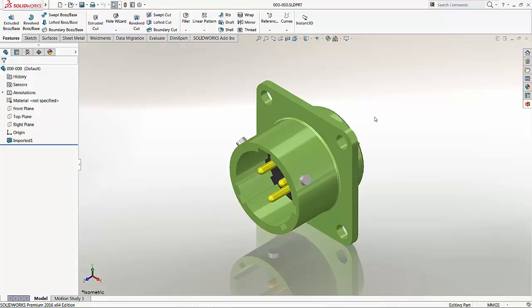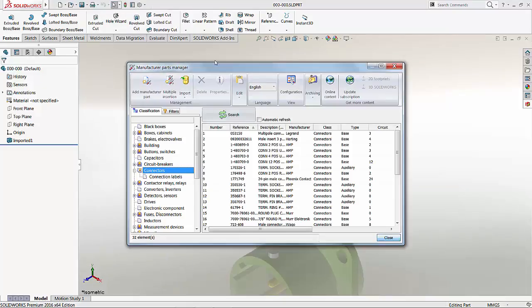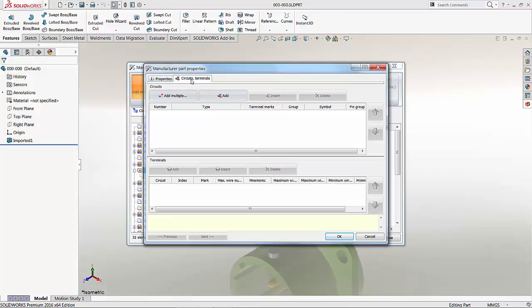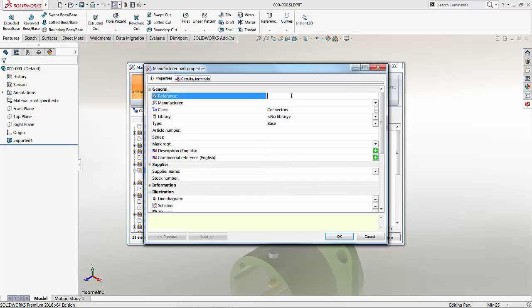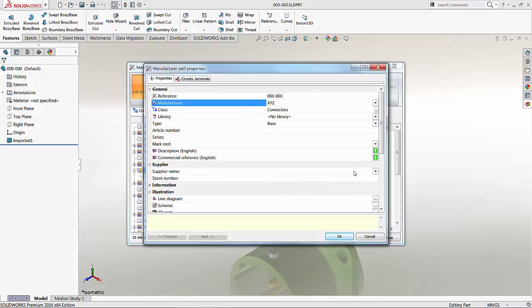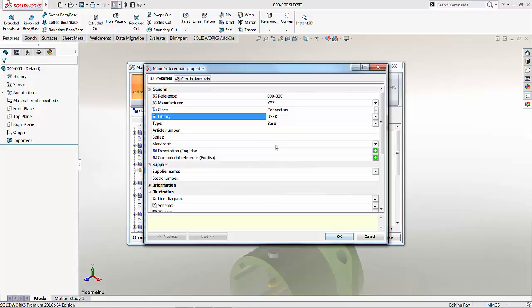Next, I'm going to go to Tools, SOLIDWORKS Electrical, Manufacturer Parts Manager. This process can be carried out either in the schematic or electrical 2D, or the SOLIDWORKS Electrical 3D environment. I'm choosing to do this in the 3D environment since I've already started here. I'm going to start off by adding a new manufacturer part — creating something from scratch. There are two tabs: Properties, and Circuits and Terminals. Under Properties, I'll call this 000-000. I'll define the manufacturer — I've got a generic one called XYZ — it's going to be a connector, saved under the user library.